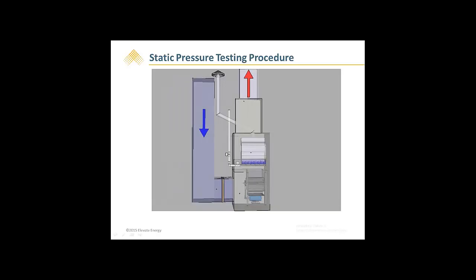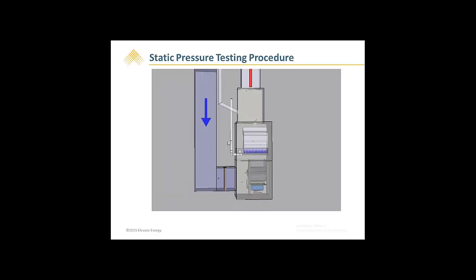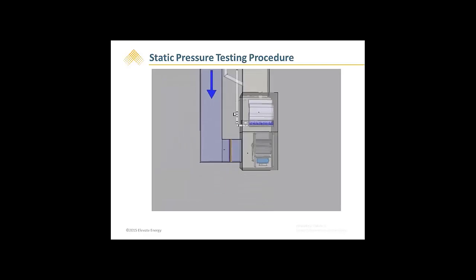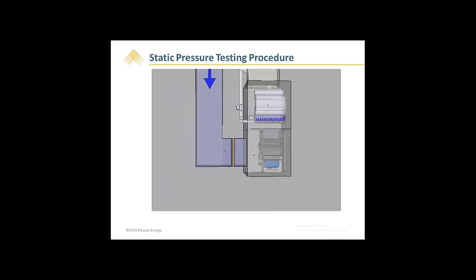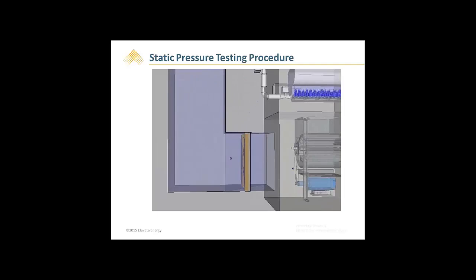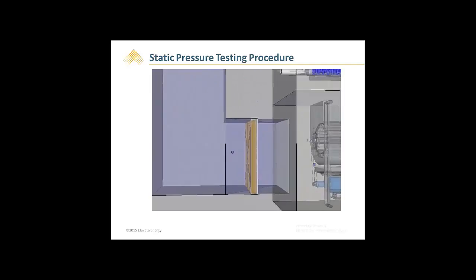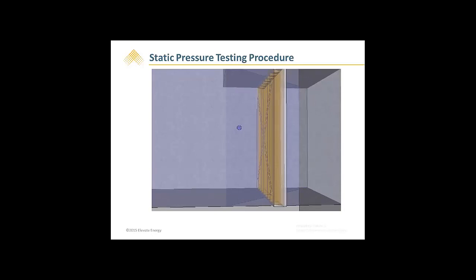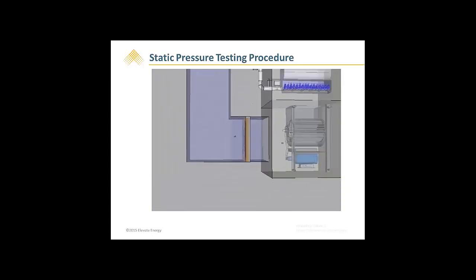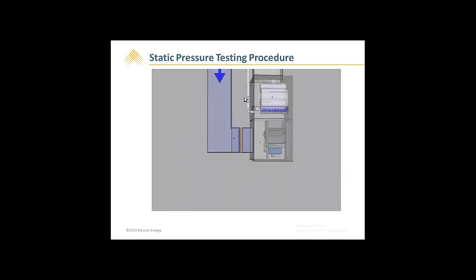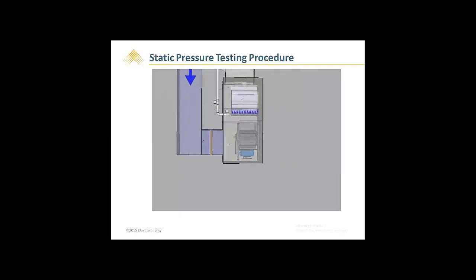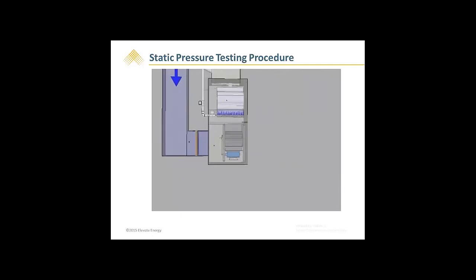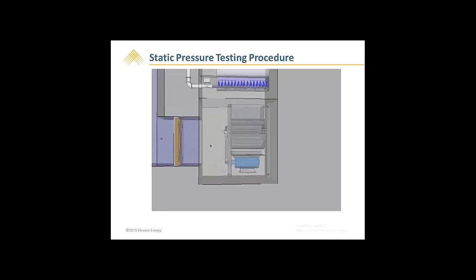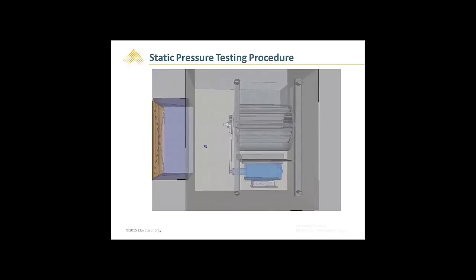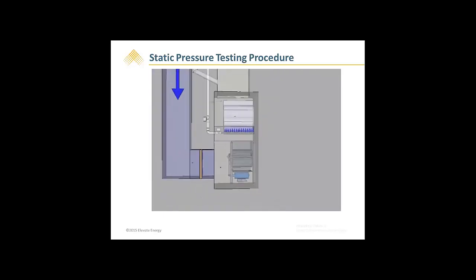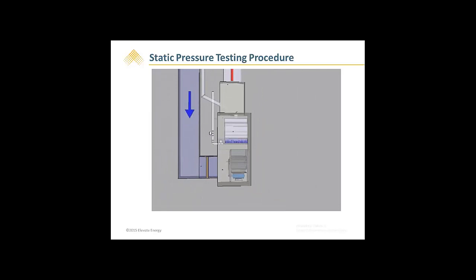Here's an example of a typical 80% efficient 4-star furnace. There are 4 measurements that need to be taken to determine the system static pressure. The first is before the filter. Please note that with all test locations, you will need to be sure that the static pressure tip is always pointing in the direction of airflow. The second test location is at the blower cabinet. When testing here, you want to be sure that none of the blower components come into contact with the pressure probe. The third testing location is at the heat exchanger cabinet.